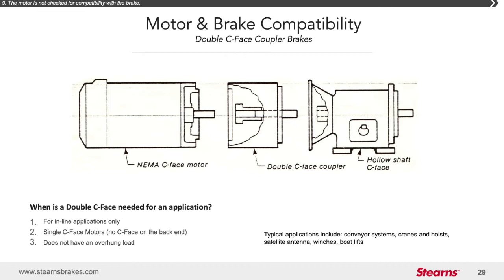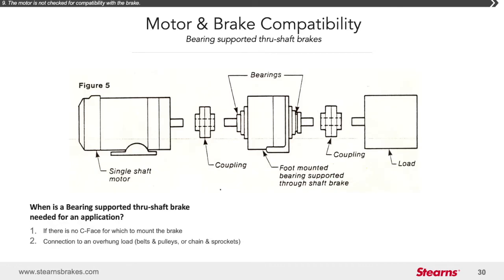However, if you have an overhung or side load application, there is another option we can consider. A foot-mounted bearing-supported through-shaft brake was specifically designed for use with overhung loads. It has dual bearing support to enable the shaft to withstand the impact of an overhung or side load.